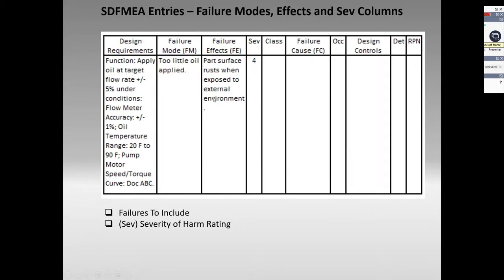Then we ask for the harm. Now, in this particular case, it's not important that you list every possible harm. It is important that you list the worst case harm. What's going to happen is if we put the worst case harm in here, we're going to over-design a little bit, because the probability of that worst case harm is going to be less than the total probability of this particular failure mode.